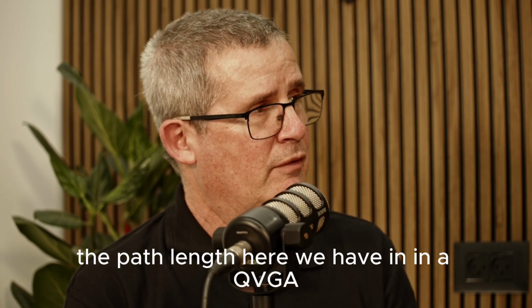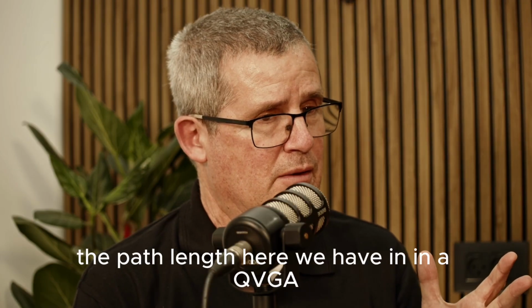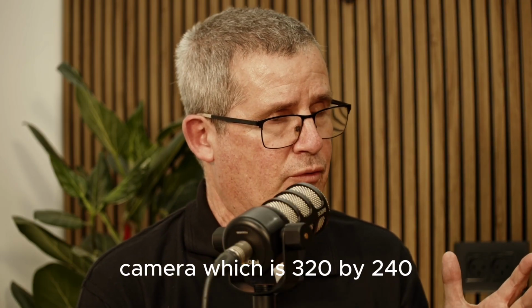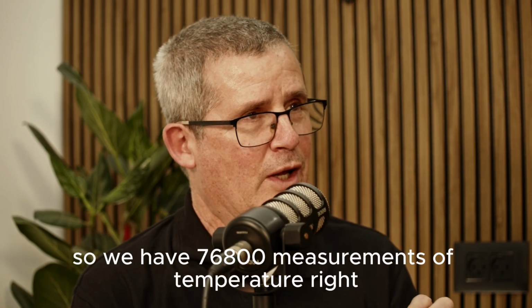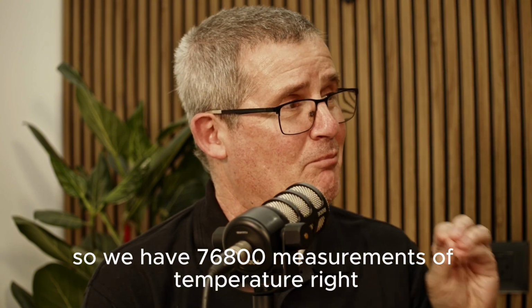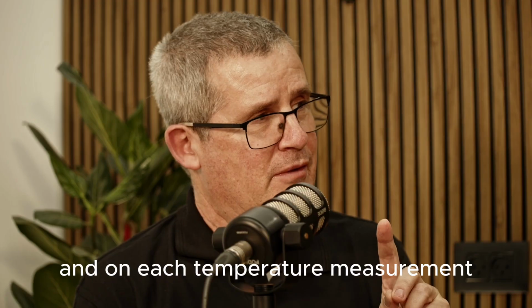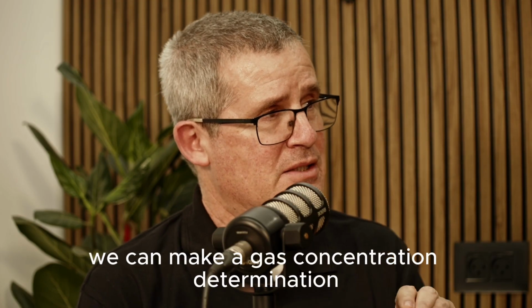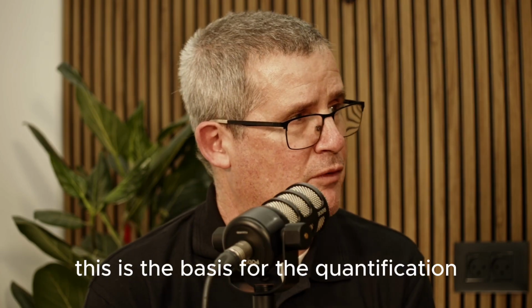Here, in a QVGA camera, which is 320 by 240, we have 76,800 pixels. So we have 76,800 measurements of temperature, and on each temperature measurement, we can make a gas concentration determination. This is the basis for the quantification.